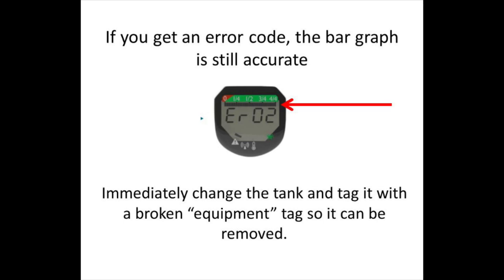When using the DISS connection for ventilators, please note that the calculations may vary significantly depending on patient effort and flow rates. The manufacturer recommends that we use the bar graph as our primary indicator of gas remaining during ventilator applications. Also, if at any point the digital display gives you an error code, the bar graph will still be accurate, but you should immediately change the tank and tag it with a broken equipment tag so we may notify Airgas of the problem.